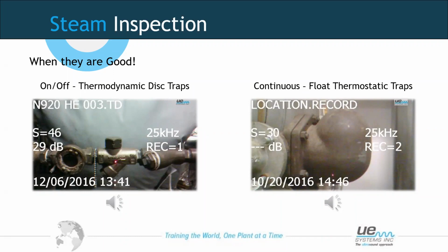So as we can hear from this sound then, we do hear the ball float knocking around inside the trap. That's because it's floating on a bed of condensate. But also in the background, we can hear the steady flow of turbulence, which tells me that this trap is good. So when a trap does fail, one of the most common ways it fails is in the open position.